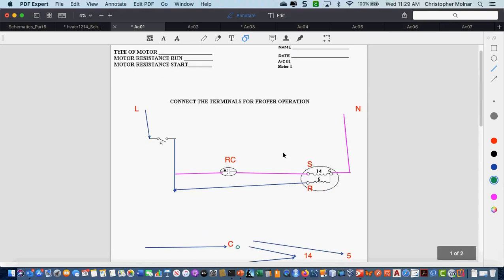Okay, so that's the capacitors. Now, back to this motor diagram. Thermostat calls for, in this case, let's make a slight change to that thermostat. Let's make it into a heating thermostat, okay? So the thermostat calls for heat. It closes. It provides power to my run winding.